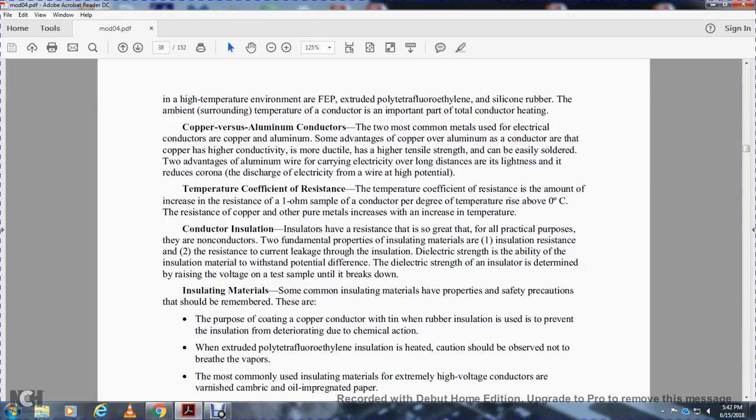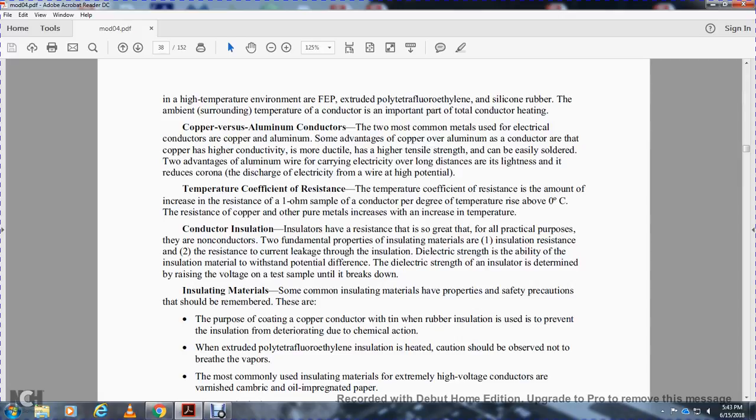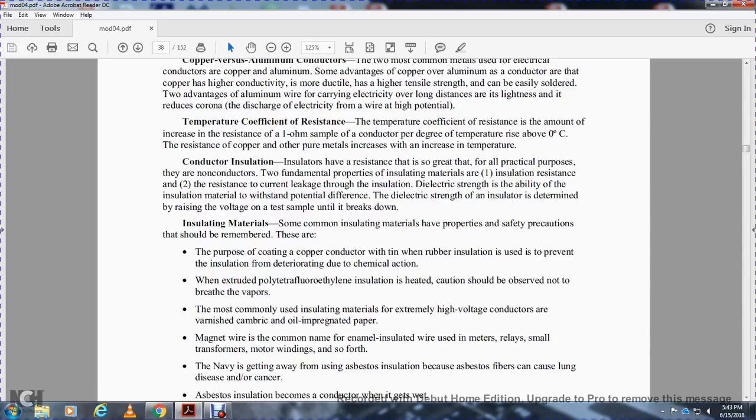Conductor insulation. Insulators have resistance that is very high for all practical purposes. Two fundamental properties of insulating materials are insulation resistance, which prevents current leakage through the insulation, and dielectric strength, which is the ability of the insulation material to withstand potential difference. The dielectric strength of an insulator is determined by raising the voltage on a test sample until it breaks down.